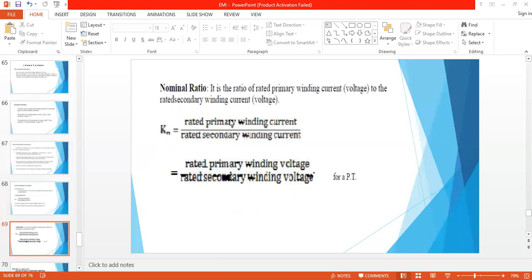Coming to the nominal ratio, represented as KN. For a current transformer, KN equals the rated primary winding current divided by the rated secondary winding current. For a potential transformer, KN equals the rated primary winding voltage divided by the rated secondary winding voltage. The nominal ratio uses rated values, i.e., the nominal values.